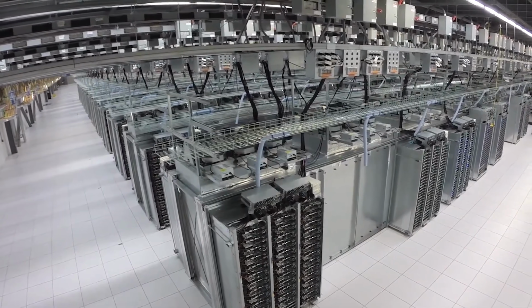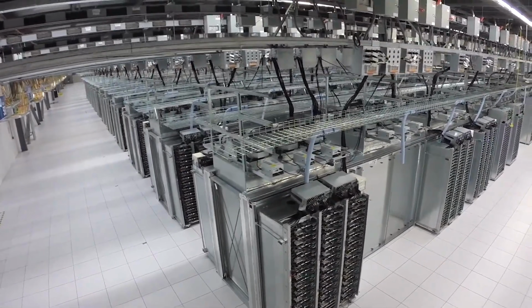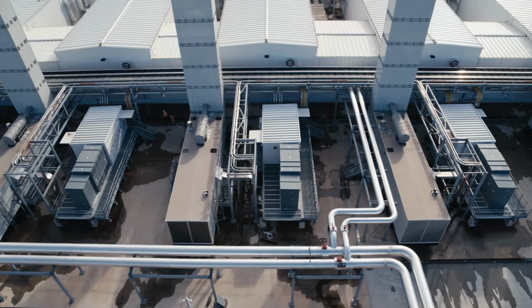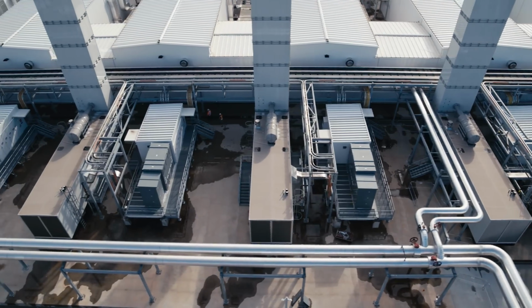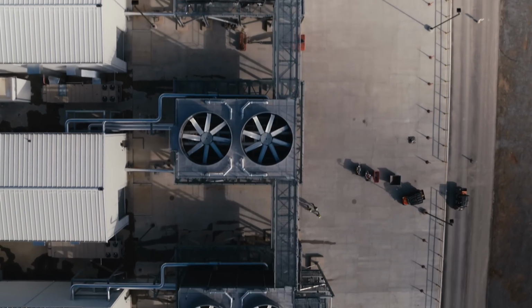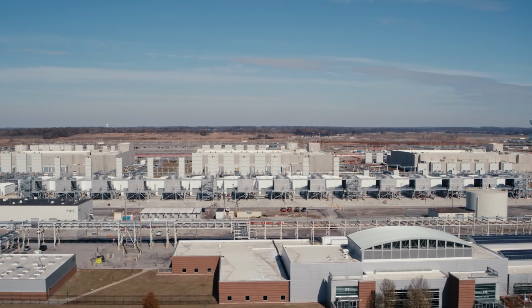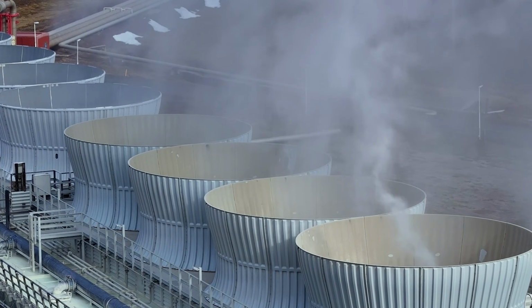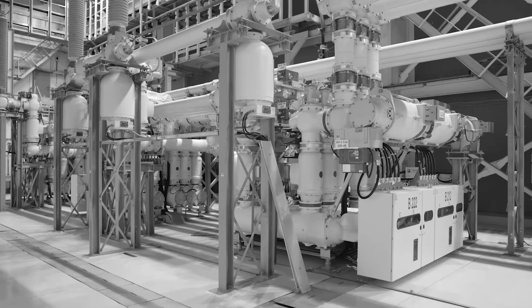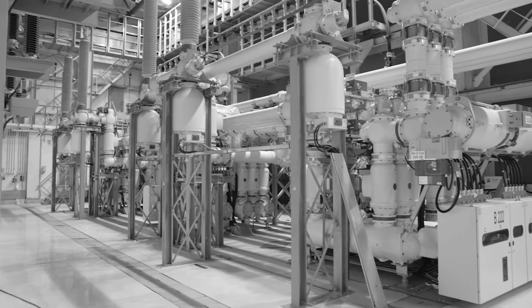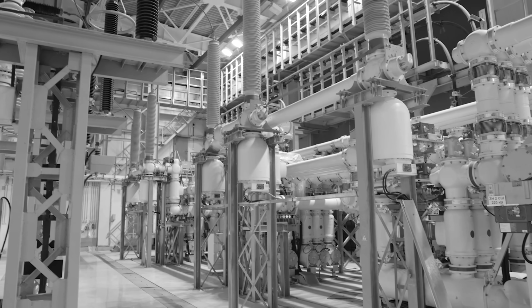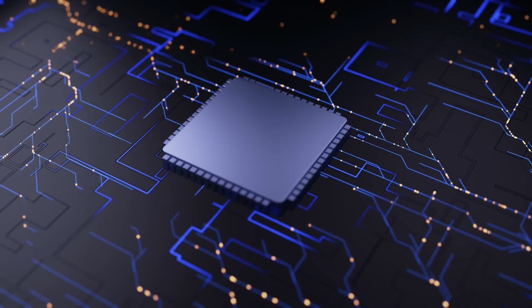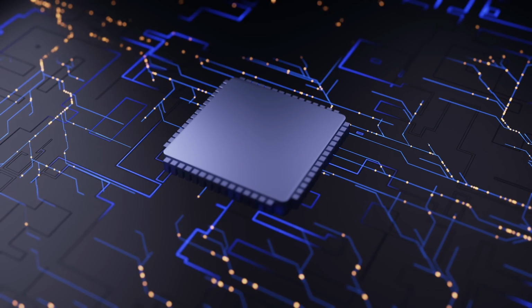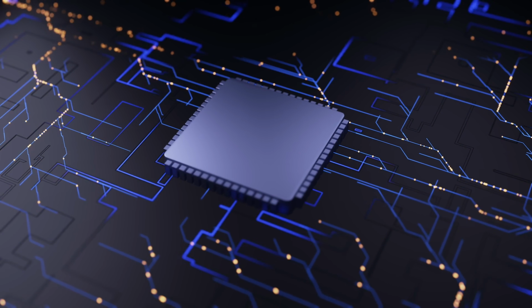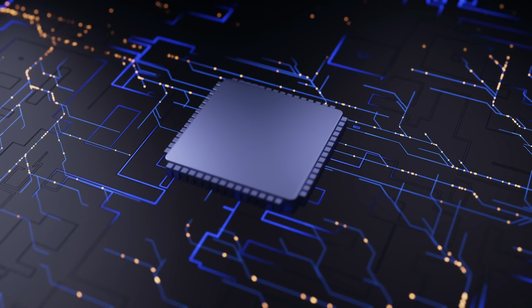There's a second layer of risk that deserves serious attention, and it's the technological one. Data centers are not neutral infrastructure in the way a warehouse or an office building is. They are built around specific power densities, cooling architectures, and floor load specifications. A facility designed 5 years ago for average rack densities of 8 to 12 kilowatts per rack may be structurally and mechanically incapable of supporting the 50 to 100 plus kilowatt densities that modern AI workloads require.